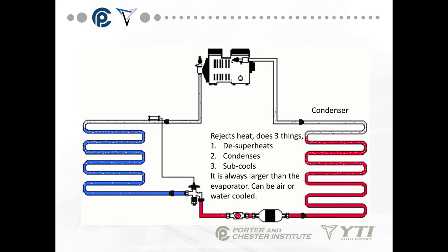The condenser is the next part. What it does — it actually rejects the heat. Our whole purpose of air conditioning is to take the heat from a place we don't want it, which is the inside of the building, and move it to a place where you do want it, which is outside. The condenser moves the heat out of the refrigerant into the outside environment — it desuperheats, condenses, and sub-cools.